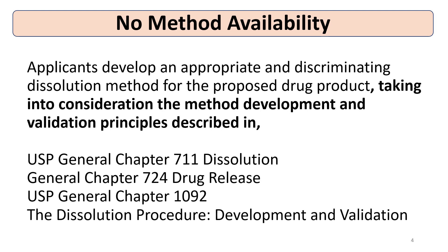If there is no Dissolution Method available in the monograph, no monograph exists, or no method is available in the OGD, then the applicant is required to develop an appropriate and discriminatory Dissolution Method for the proposed drug product. This must take into consideration the method development and validation principles described in USP General Chapter 711 for Dissolution, USP General Chapter 724 for Drug Release, and USP General Chapter 1092 for Dissolution Procedure Development and Validation. All these USP chapters are required to be referred to, and on the basis of their principles, the Dissolution Method must be developed.